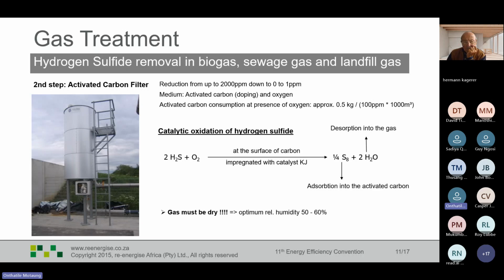So the gas must be dry, so you cannot actually treat a saturated gas with activated carbon. In most cases, where you have, for instance, either a compressor or a blower just after the chiller, that will help with increasing the temperature of the gas to reduce relative humidity from 100 to between 50 and 60, because that's what we desire. But if you don't have a compressor or a blower between the chiller and the CHP, you can use a heat exchanger to make sure that you reduce the relative humidity of the gas.